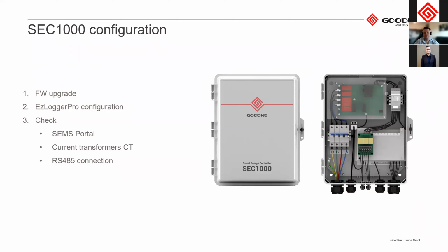So normally you'll be installing this nearby your connection point, and especially on commercial sites, that is very often outside somewhere or off to the side of one building. And it's very important to install this as close to the connection point as possible. So for full accuracy of your CT readings, you don't want to have your CT cables really longer than 5 meters, because the longer your CT cables are, the more accuracy you lose, as well as the voltage reference point.